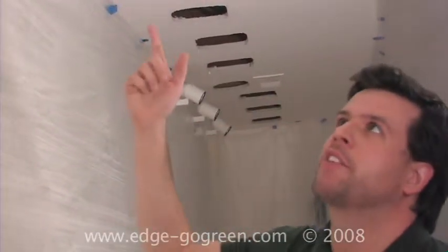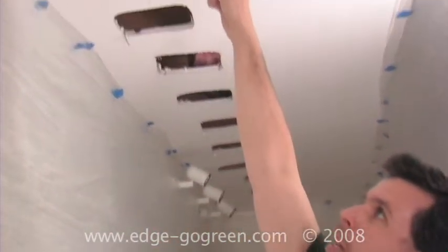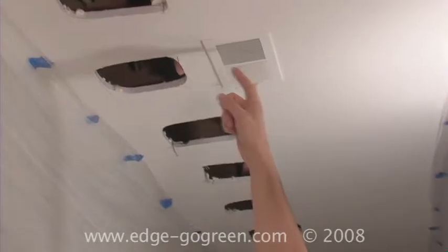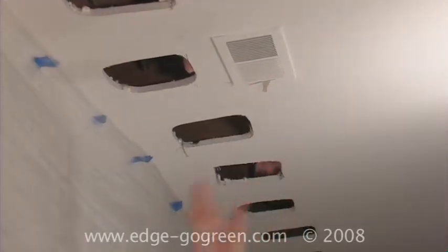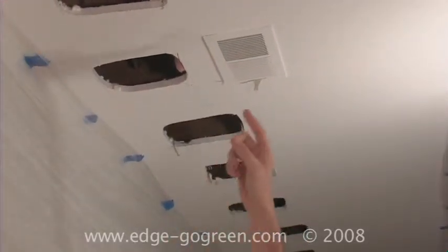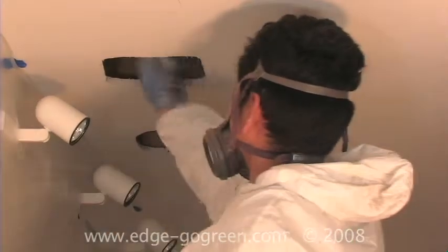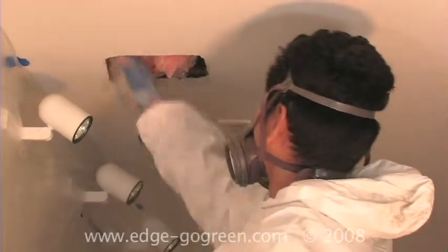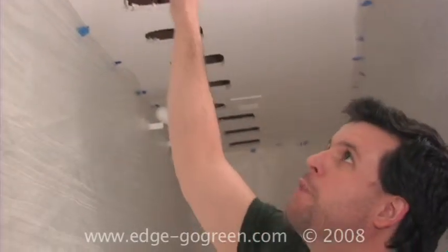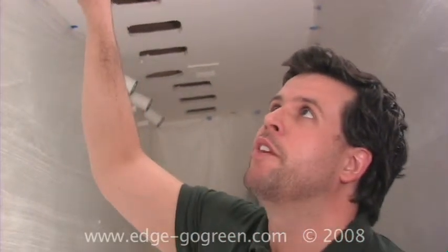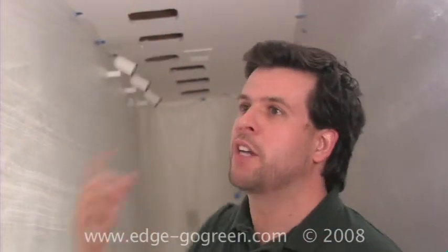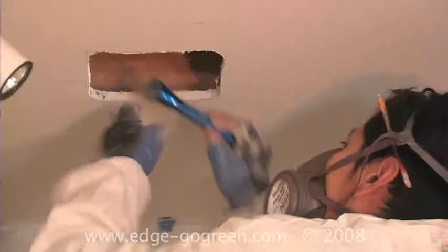When we have access to the band and rim joist, it gives us the opportunity to inspect HVAC registers and associated ductwork to make sure they're properly sealed and connected. In this ceiling, for instance, we've got HVAC registers in the ceiling and also in the floor of the main level above, so there's actually double ductwork in these floor joist cavities. Opening up all of these lets us inspect the register boots and make sure the ducts are well connected to those registers - something we might not have been able to do if we didn't open up this section.